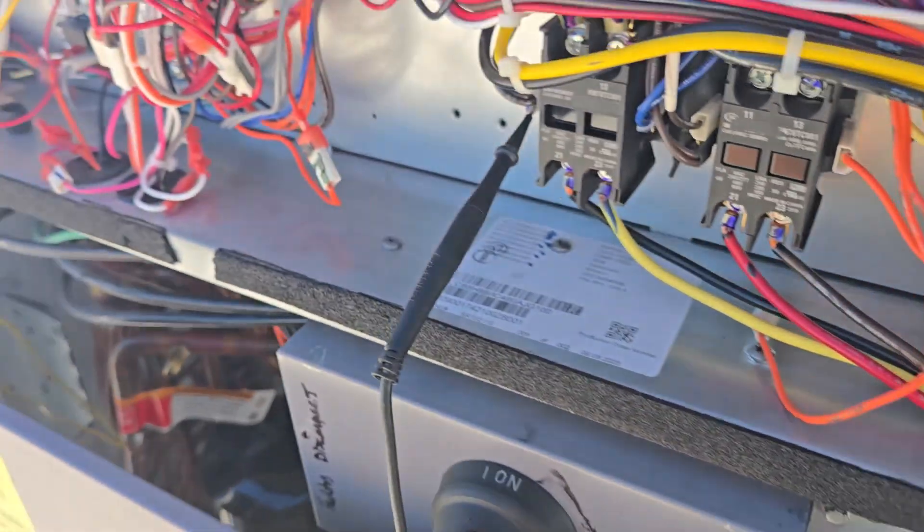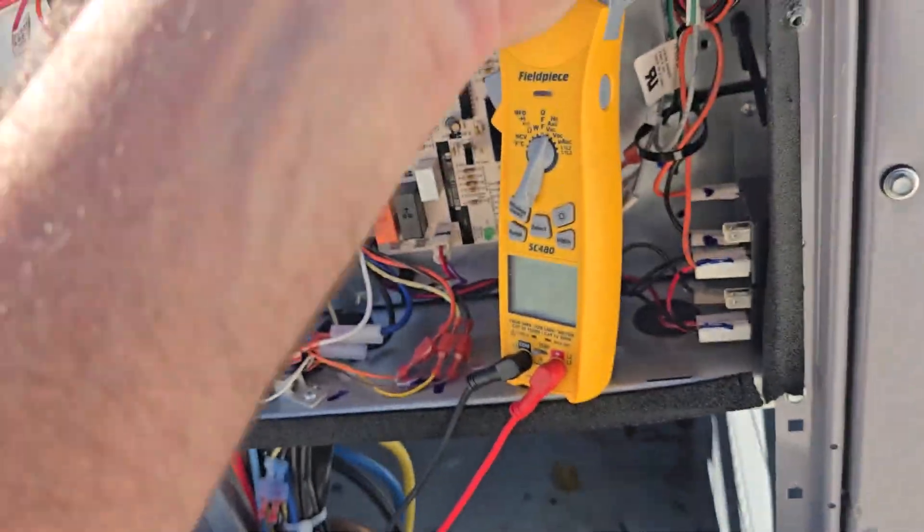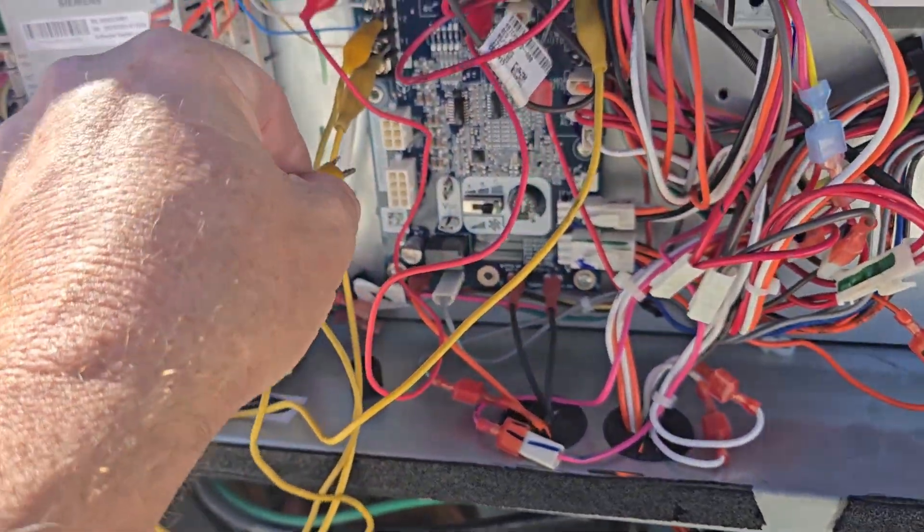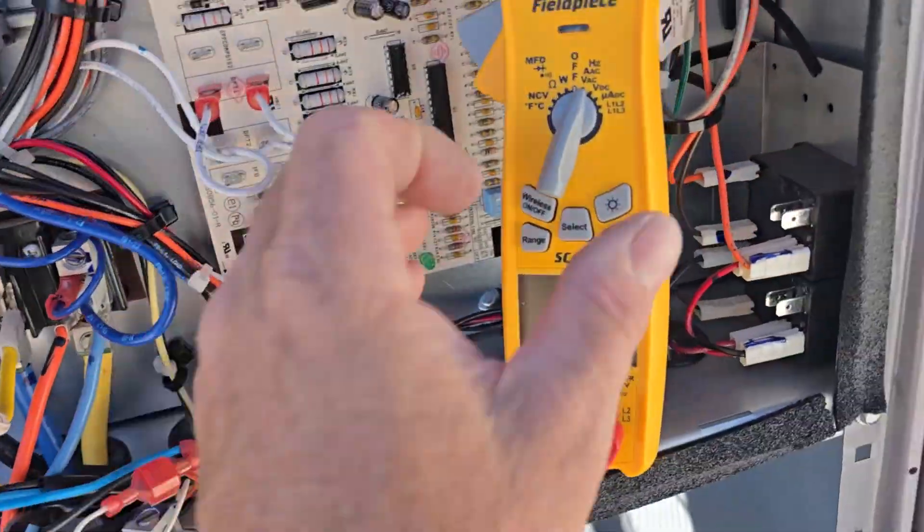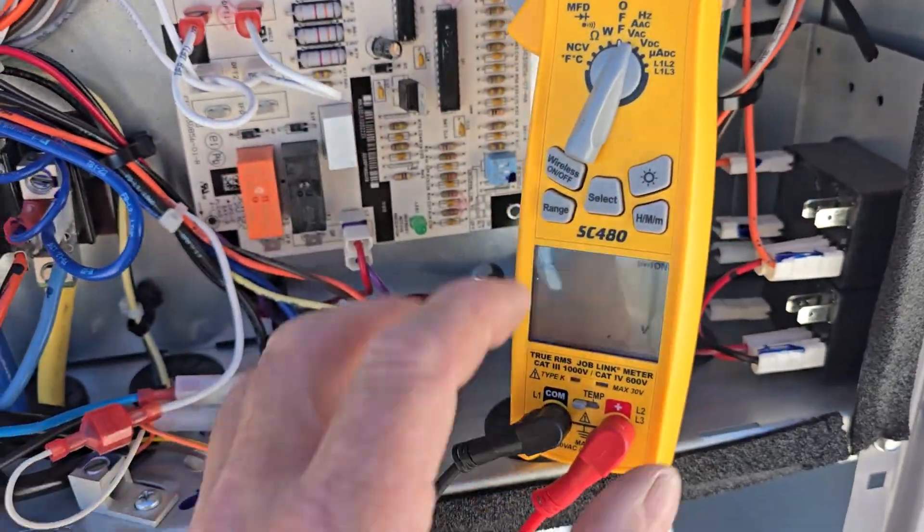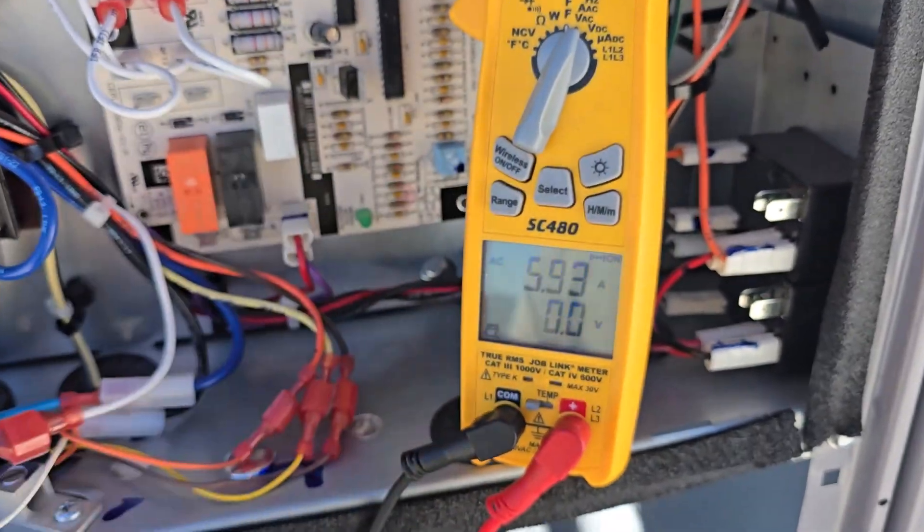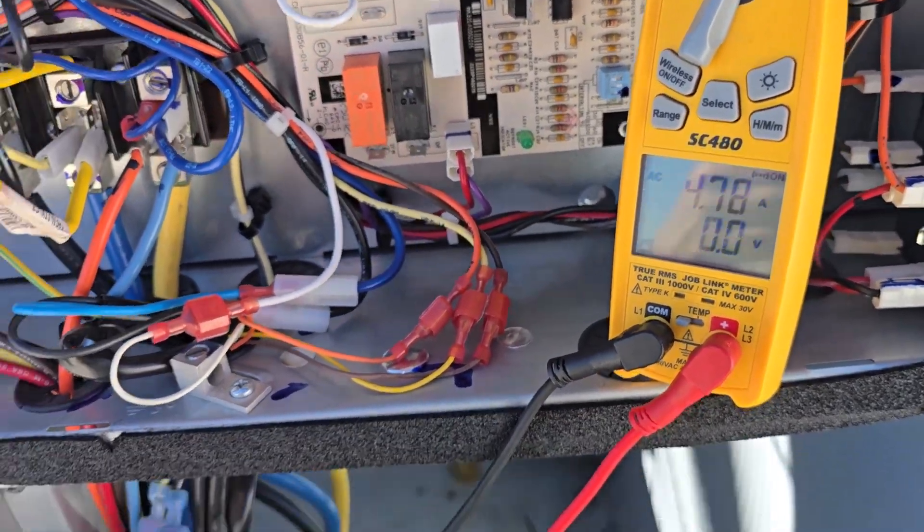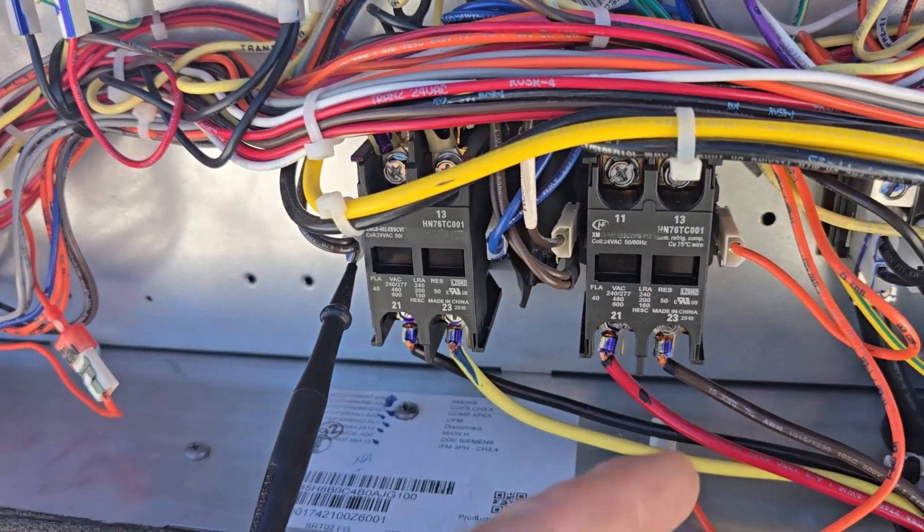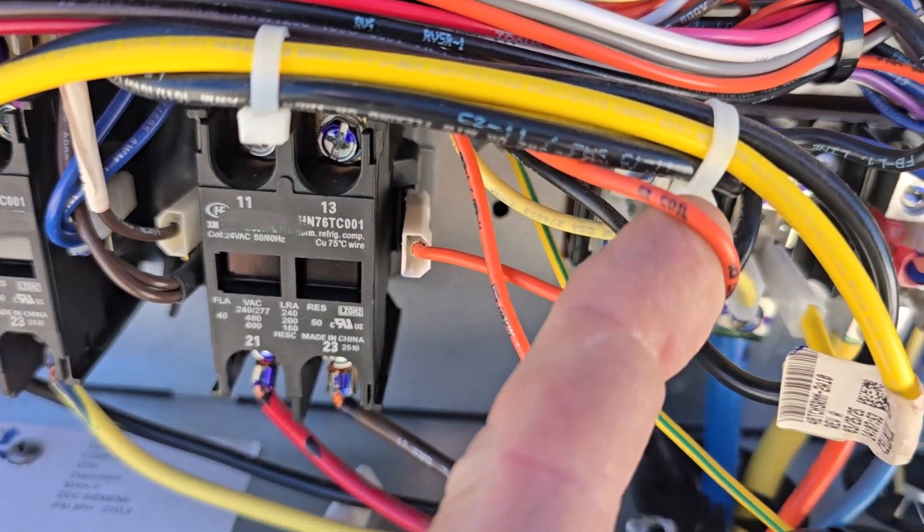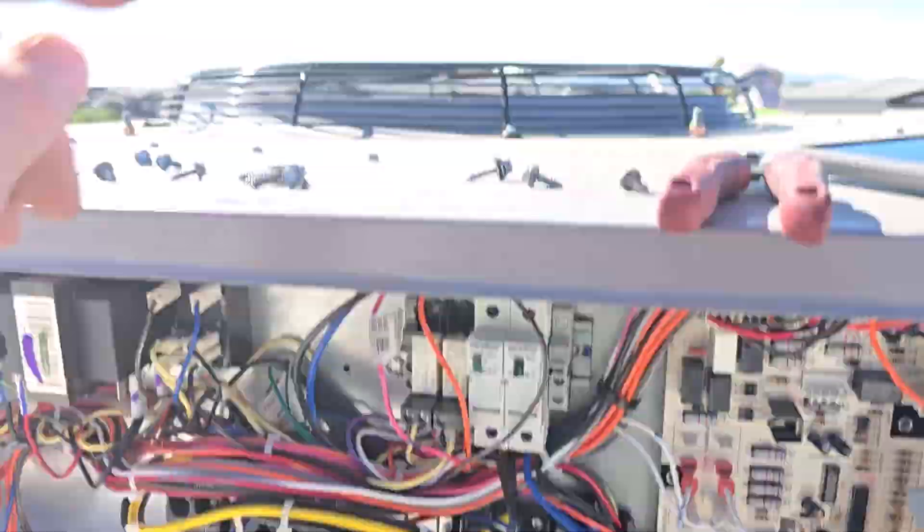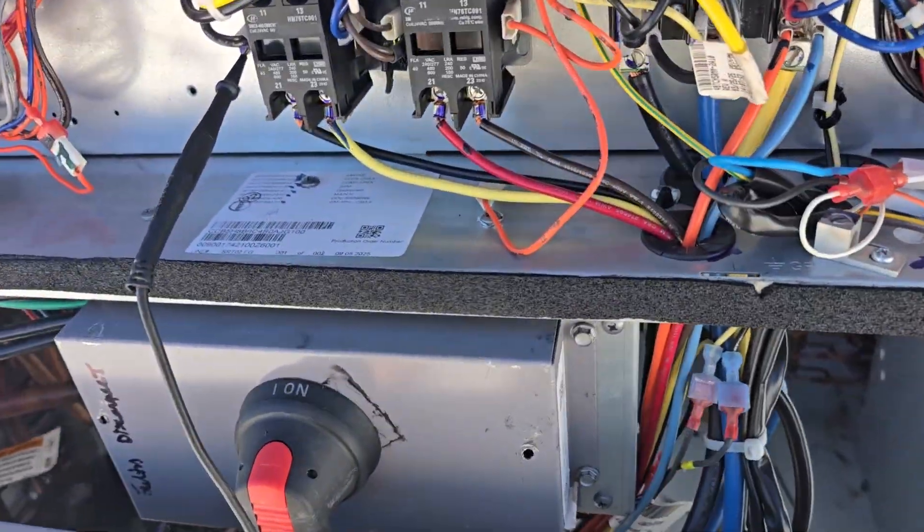And now to test it that disconnected like it should be. If I bring on Y2 now, by the way the fan speed was one amp, now the fan speed shooting way up. Now the second contactor is energized properly through the one. It's a C2 coil. This comes out of that other pin I showed you. And there goes that fan, ECM's just roaring to life.